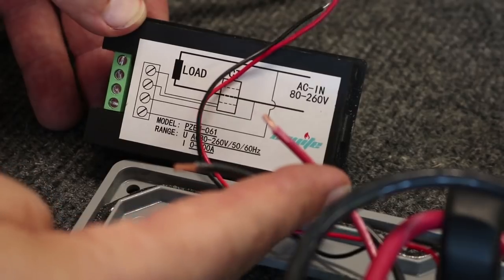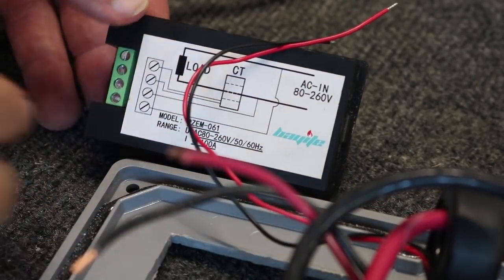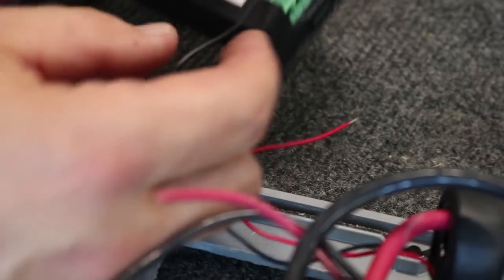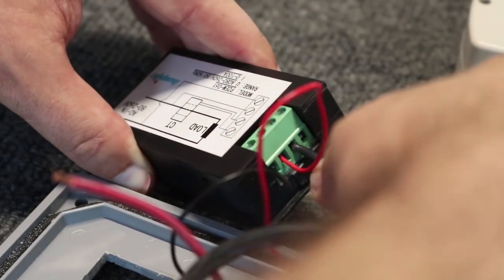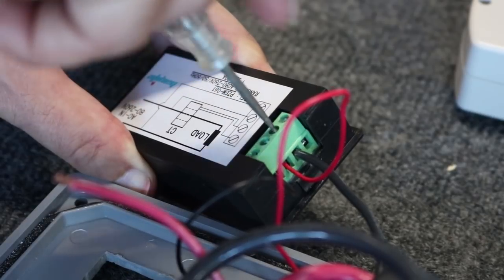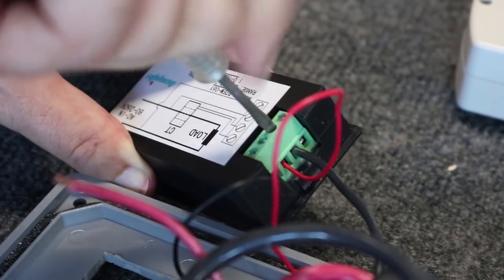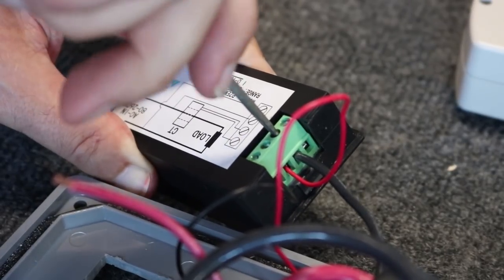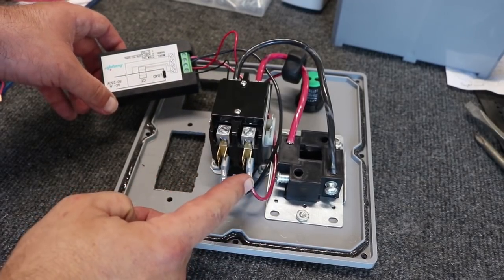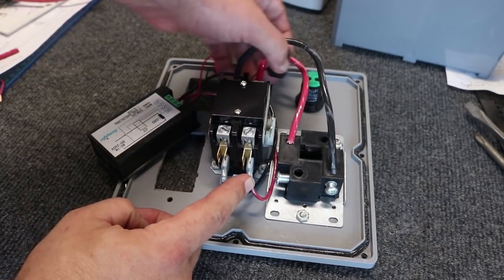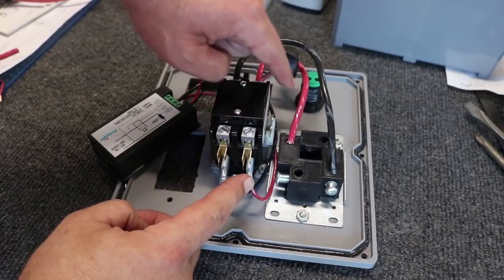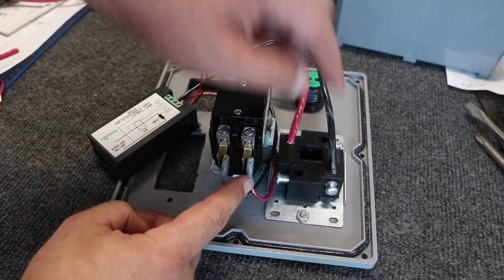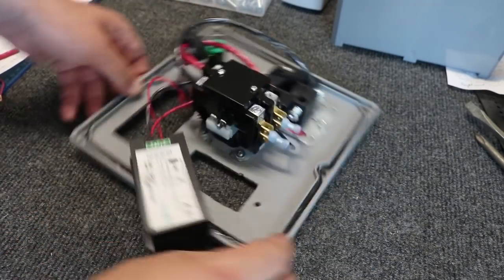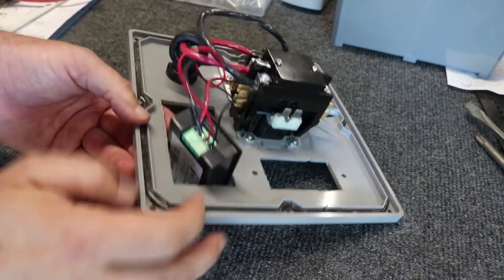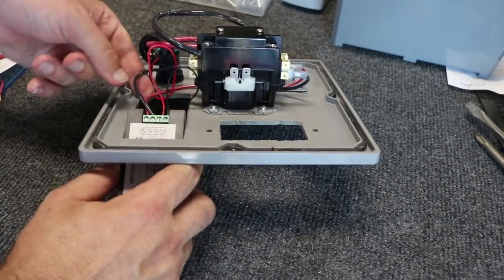The other thing I found out with these is it's not obvious which way is up. So look on the front, the little button is on the right-hand side. Don't install it upside down. The two power wires come up from the contactor, and then the current transducer is just on that one heavy red wire on the output end of the contactor. And what that does is it means we're only measuring the power from the contactor, not the meter or the light that I'm going to add or anything else. And we just have to turn the meter to get it through the hole, and then we can pop it down into place.